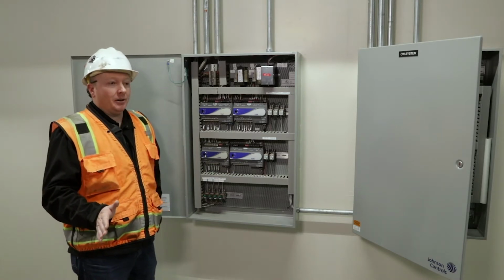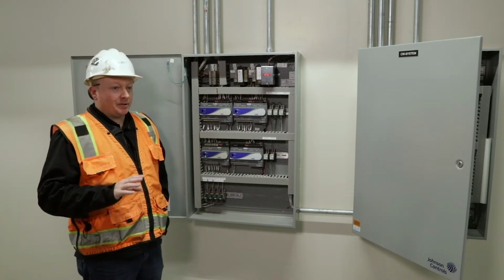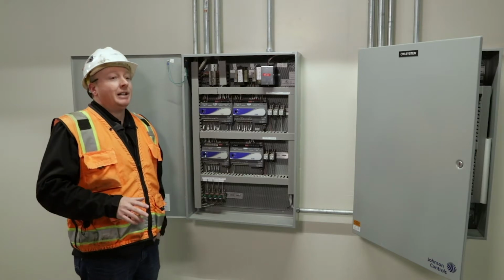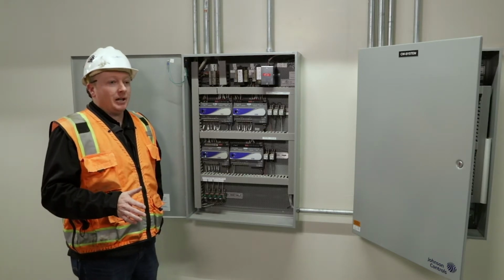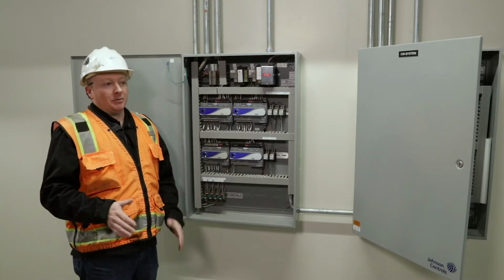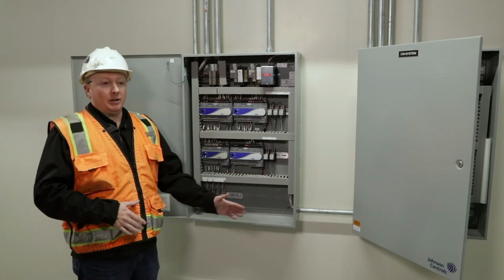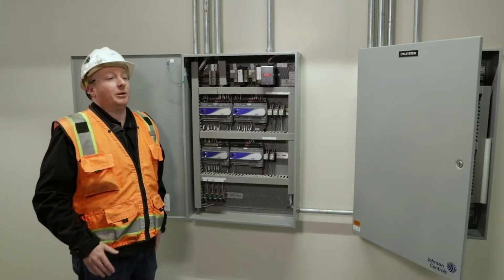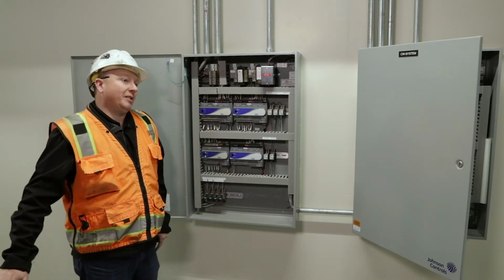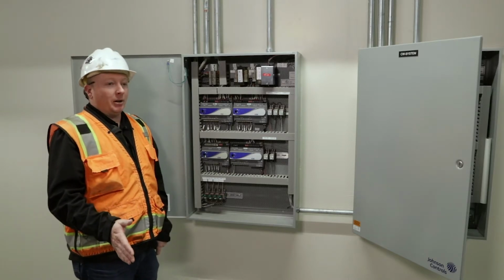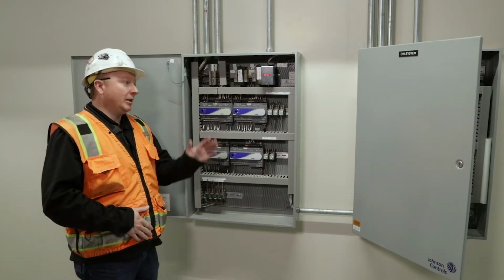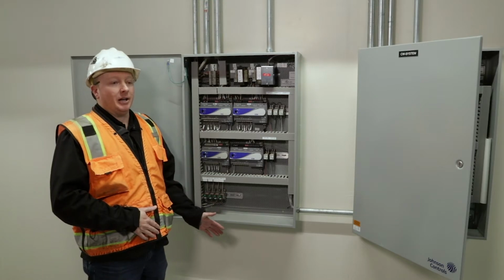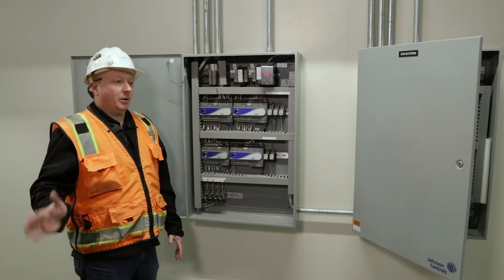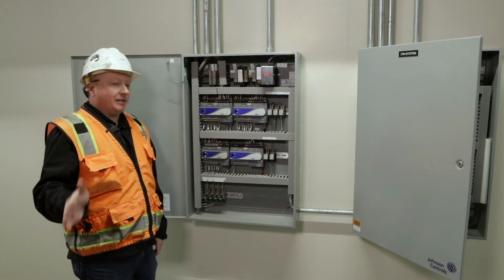All your pumps are headered, so you have 3 condenser water pumps, 3 primary chill water pumps. They also rotate based on runtime, so there is no direct relationship with pump 1 goes with chiller 1 or anything like that. We are starting a chiller, we're picking the primary chill water pump with the lowest runtime, condenser water pump with the lowest runtime, and then away we go. We have isolation.